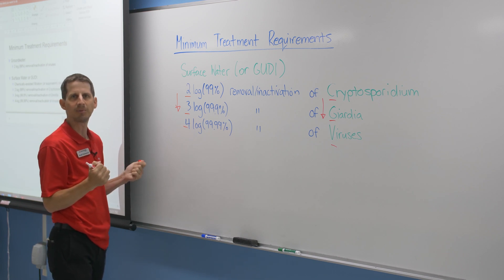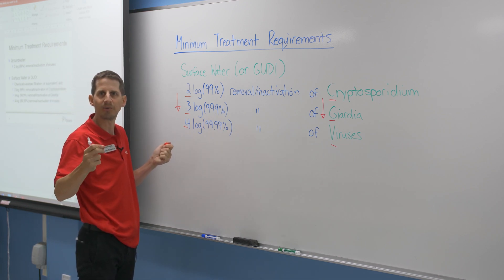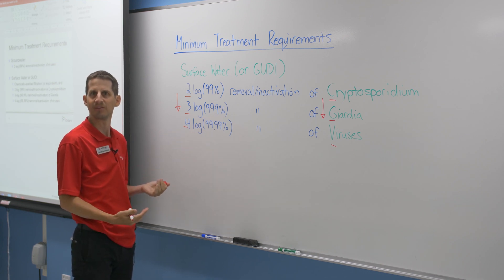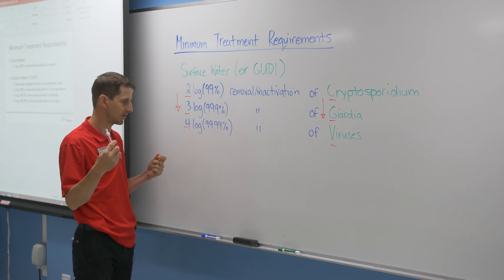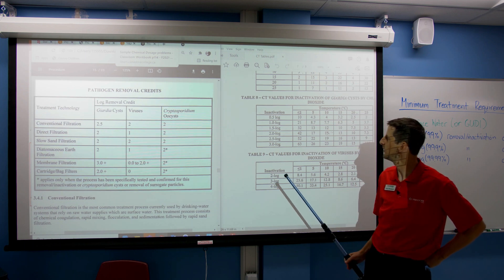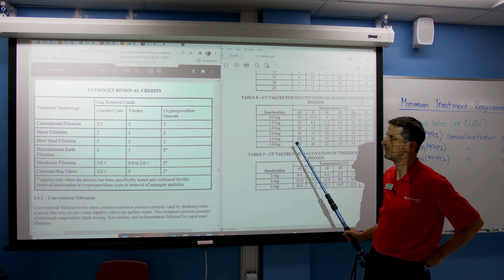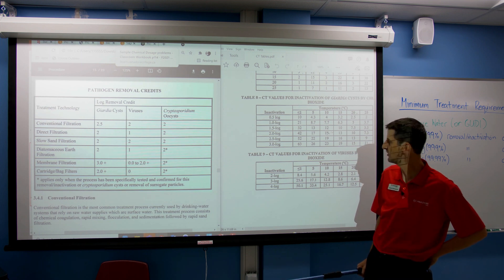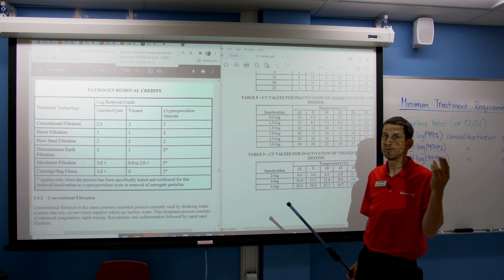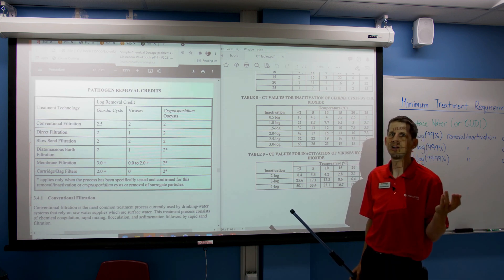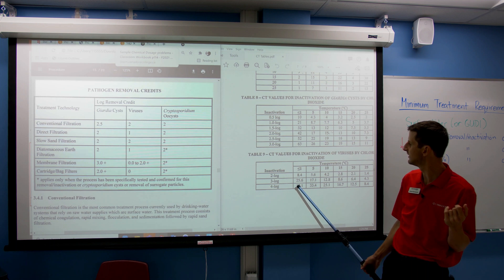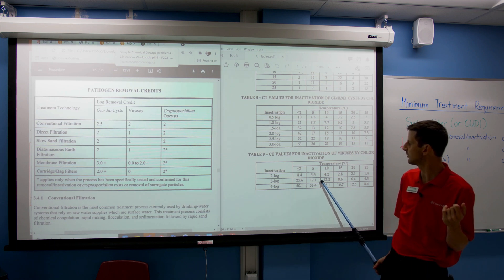Let's go back and look at the CT tables, because we have to choose what log removal we need. And we're thinking, well, if it's two, three, four, why is there 0.5 and 1.5? Let's make a little more sense of this. We have a selection of CT tables here, and you can see there are different log values for determining your contact time or concentration. We know we need four log removal of viruses, and this table here is looking at viruses — so we look at the four log removal value.